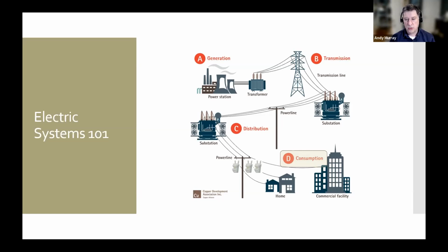Another thing to touch on with the electric system is that protection and controls are typically described as mature technologies - I'll probably bring this up several times - this equipment is expected to be in service for 20 years, maybe longer. So the change in technology is slower for a couple of reasons: you're looking at 20 plus years before you'll need to change something out, and you have to be confident that what you're picking will have a lifespan of that 20 plus years and be maintainable for it.